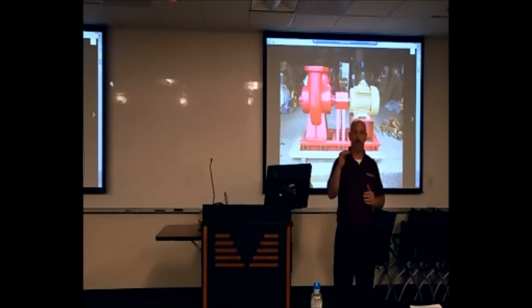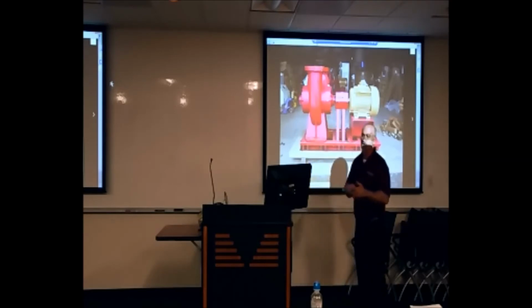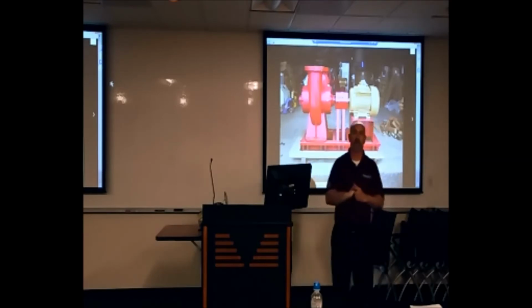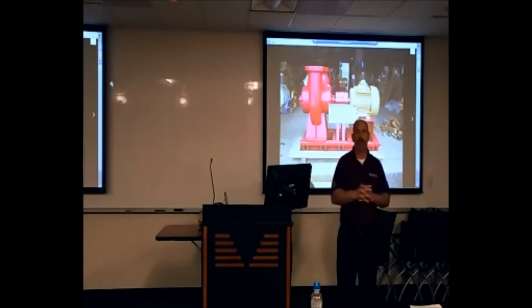It doesn't take much to go from 1/2 pound to less than 0, or below suction, and cause a suction in that line. Once that starts to happen, it will start to tear apart the internal impeller on this. It'll start to look like Swiss cheese. And that's probably the biggest mechanical failure that could happen on a condenser water pump.